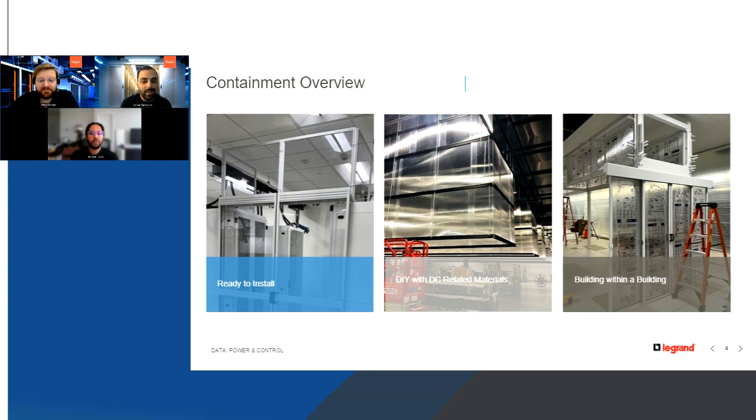And on the last one, it's really about speed to deployment. I know a lot of the hyperscale clients are using this type of material. The building core and shell goes up very fast, even as fast as 6 months, and basically you have your data center environment at the pod level rather than a whole building surrounding and supporting that. In general, these solutions are within the up to 15 kilowatt range. For densities higher than 15 kilowatts, there are a lot of cooling solutions that can be deployed. And for that, I'll pass it over to Klaus to speak to.